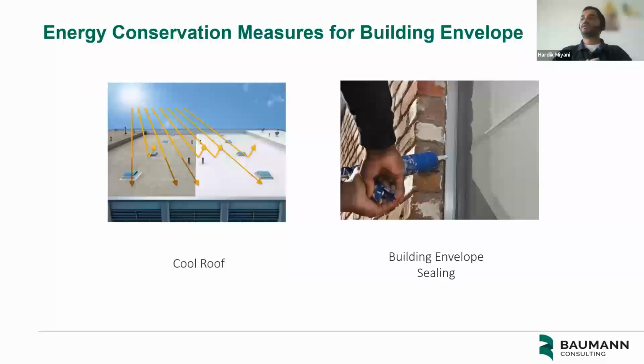And next is the building envelope sealing. Very often, for old buildings, especially 1960s and 70s construction, we see a lot of infiltration happening, be it that the weather stripping is not done on time, or there's no caulking, or the window openings are leaking. So this is a place where the majority of the conditioned air is lost into the environment, due to which the energy consumption goes up. So by providing a proper building envelope and sealing those, it can help you to save a lot of energy.